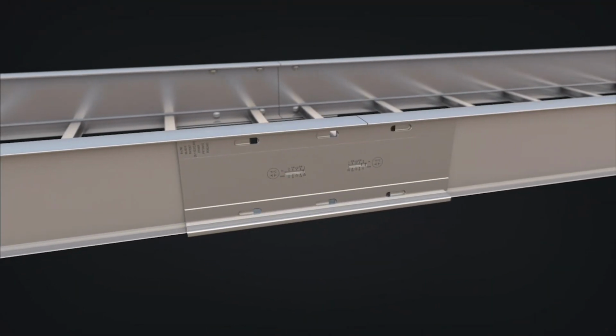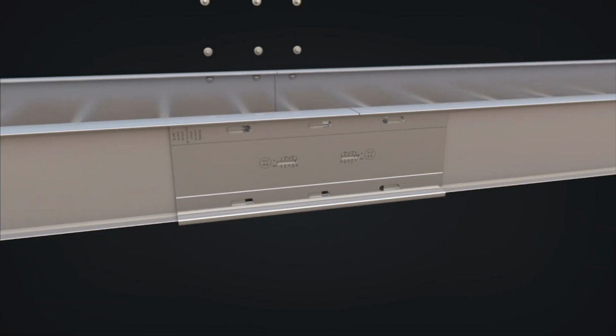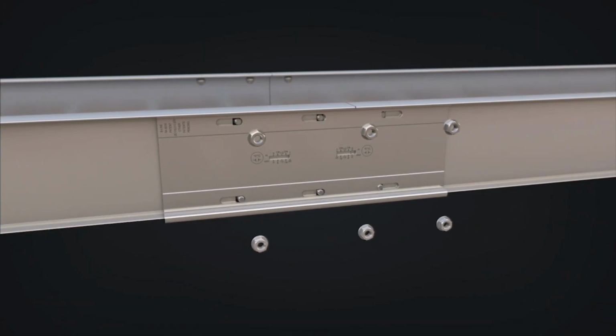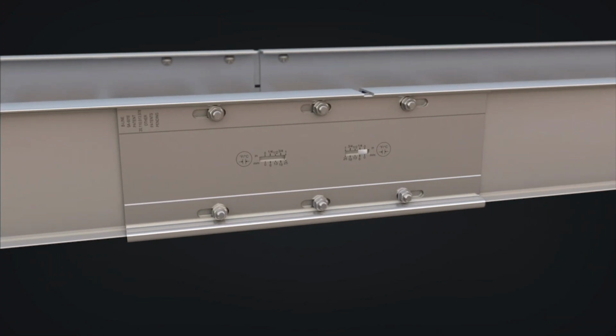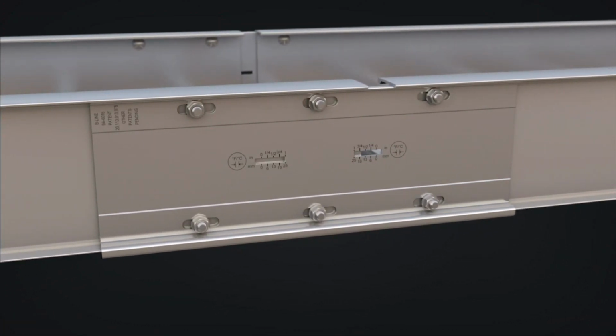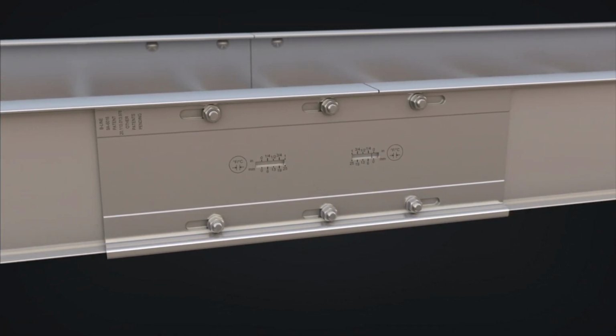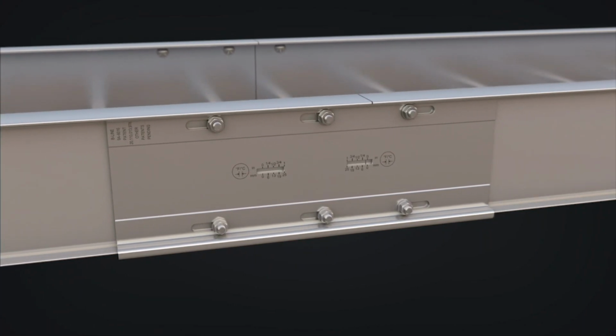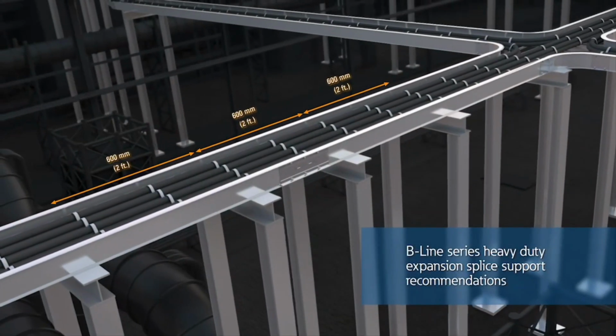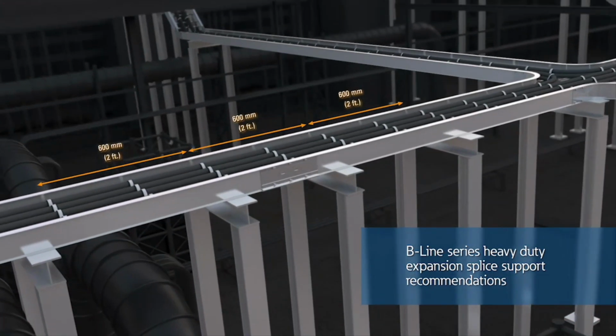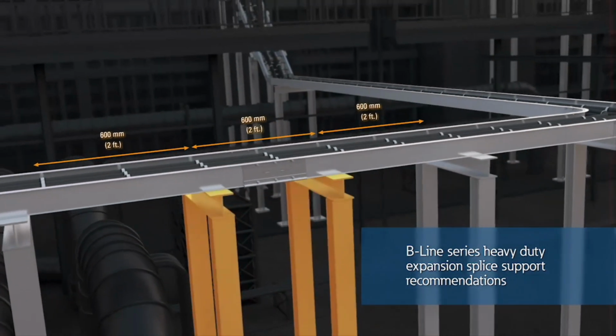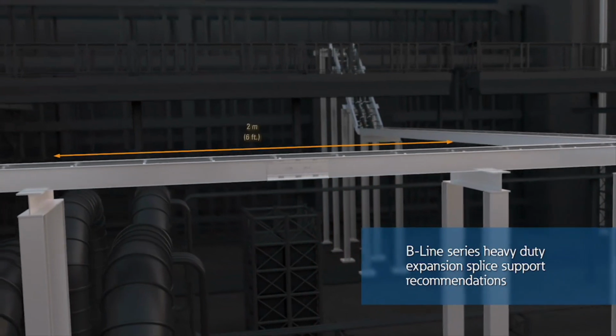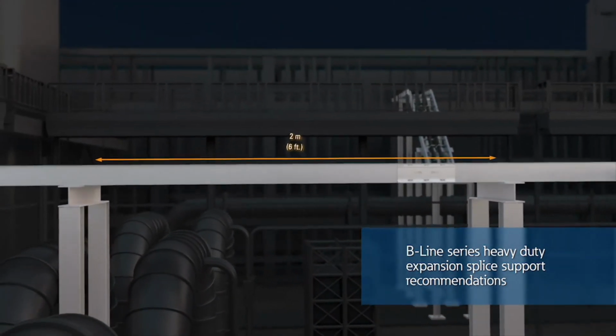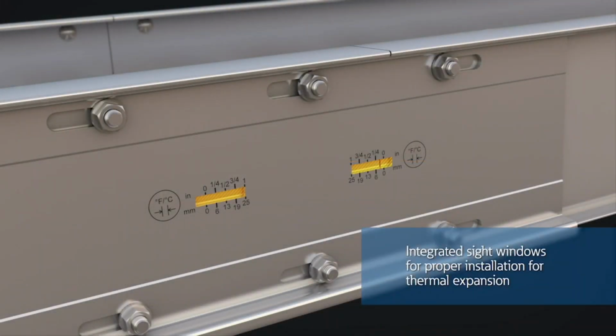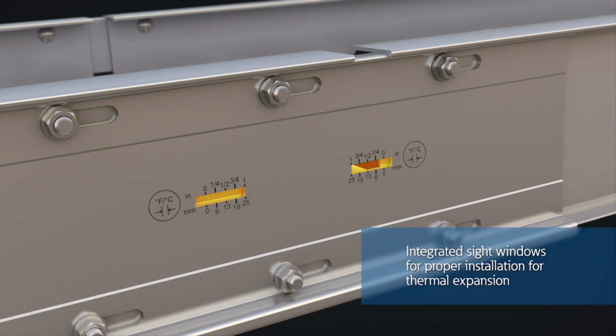Lastly, Eaton's B-Line series patented heavy-duty expansion splice solution is designed to eliminate supports and allow for proper thermal expansion with the cable tray system. The performance of the heavy-duty expansion splice, available in both steel and aluminum versions, complies with and exceeds NEMA VE2 support recommendations by eliminating the need to install 2 additional supports at every expansion location. Integrated sight windows allow for proper gap setting during installation, helping reduce installation errors.